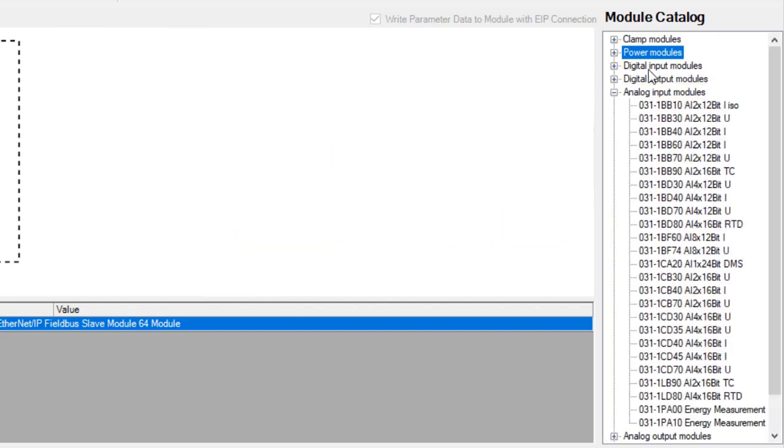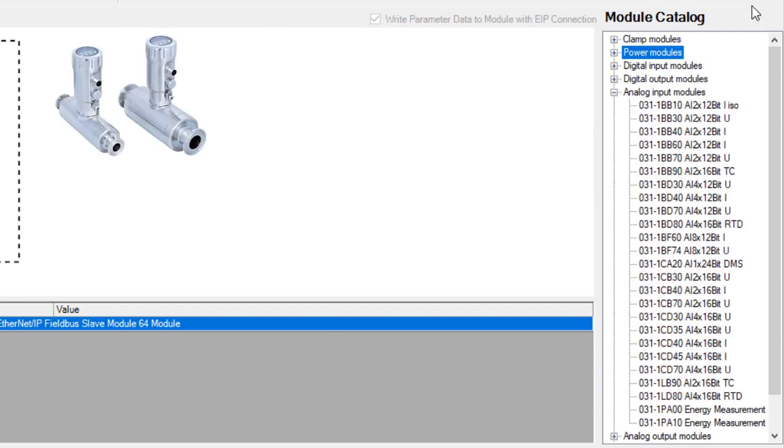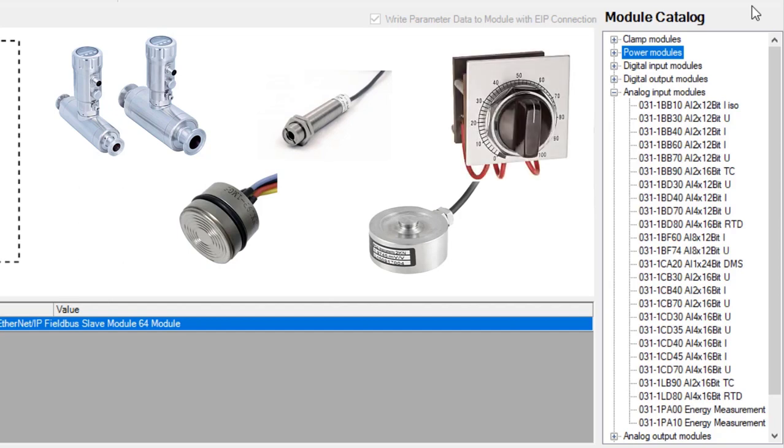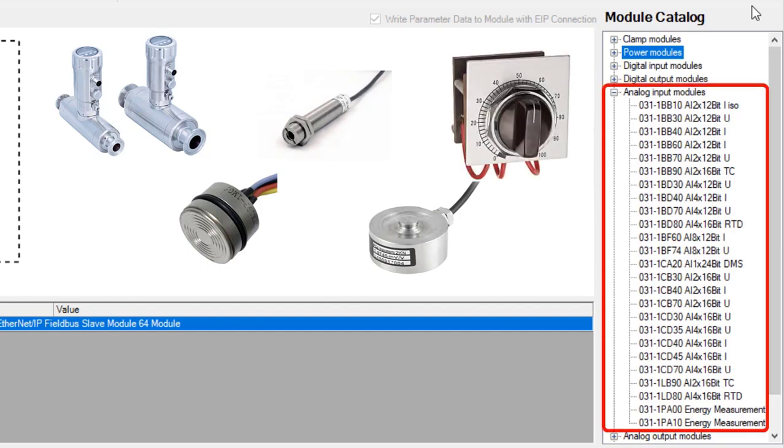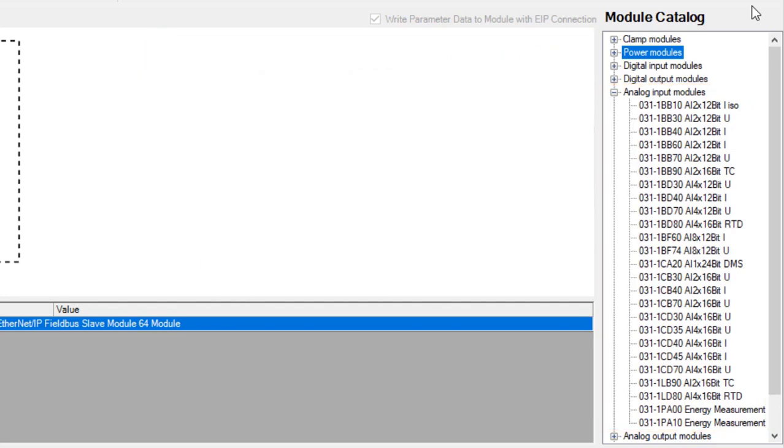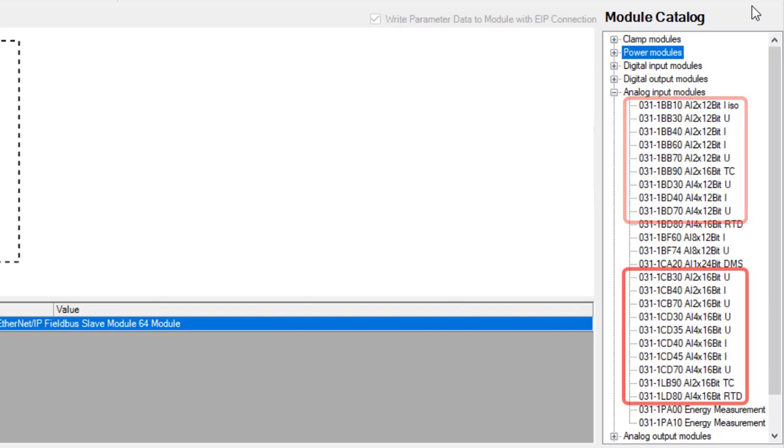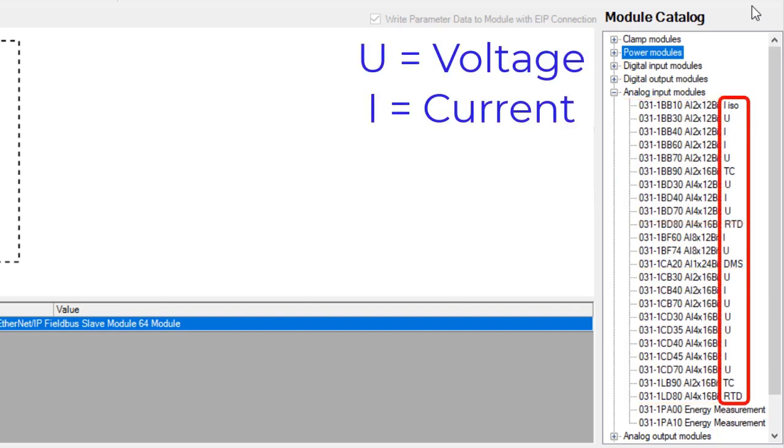Analog devices such as flow sensors, pressure sensors, temperature sensors, force sensors, and potentiometers can be used with the SLIO system using the analog functional signal input slices. The input slices can have 2, 4, or 8 inputs. The standard slices can receive analog information and process it as either 12-bit or 16-bit values. These inputs can either be voltage driven or current driven.